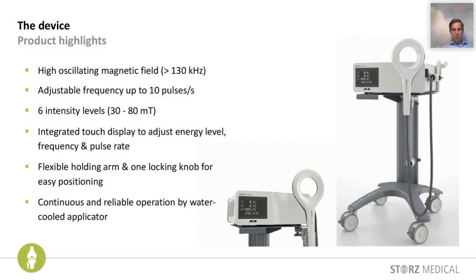You can adjust the frequency from 1 pulse per second up to 10 pulses. Basically, it's something you need to investigate yourself to find what works best for you. For me as a patient, if I'm getting 2000 pulses applied at 10 pulses per second, the treatment is over quite fast. So what you can do is go down with the frequency in order to have a longer time with the patient on the treatment couch.